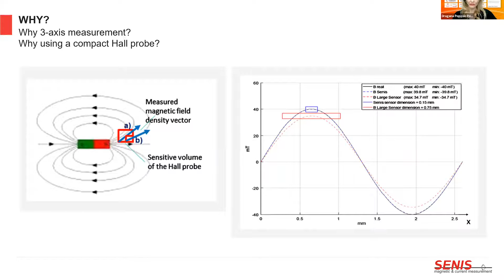Now, a few words about the calibration of the Hall probe. The sensitivity axes of a Hall sensor are never perfectly aligned with a reference coordinate system. The resulting accumulated angular errors of the sensitivity vector can be on the order of 1 degree, which is too high for modern magnetic field measurement applications. Therefore, the angular errors must be reduced, and this is done with calibration.